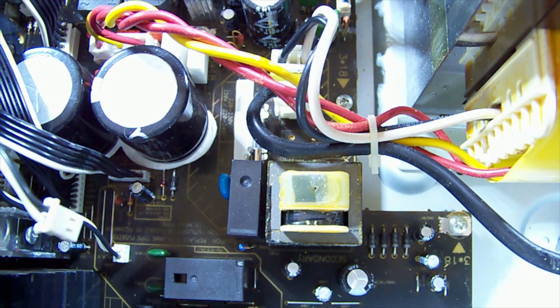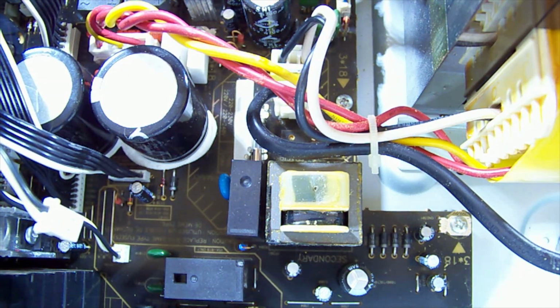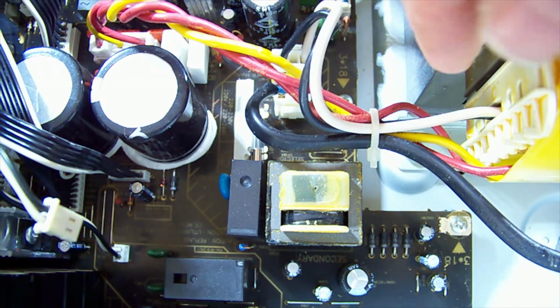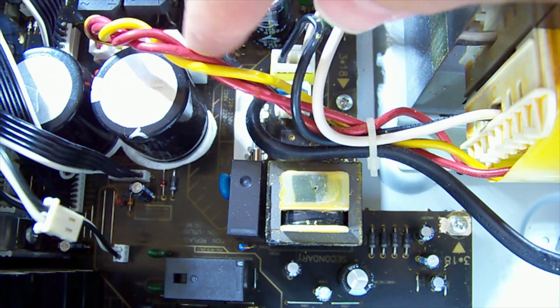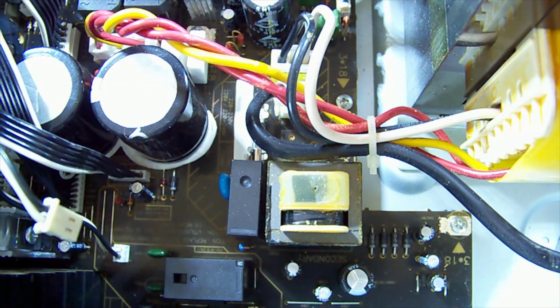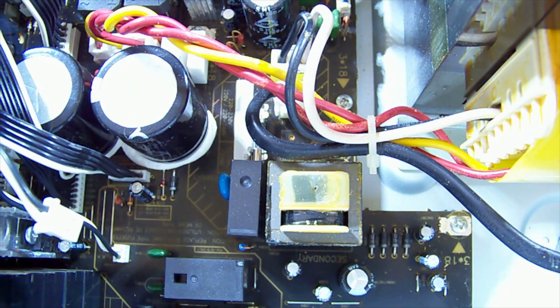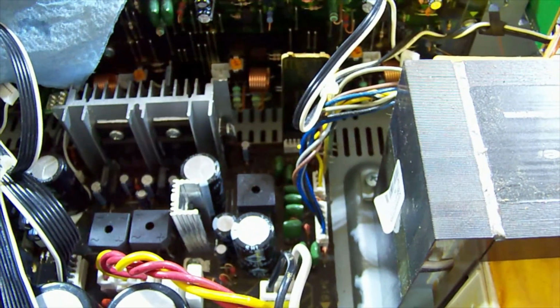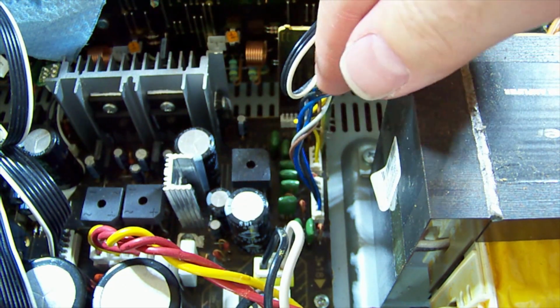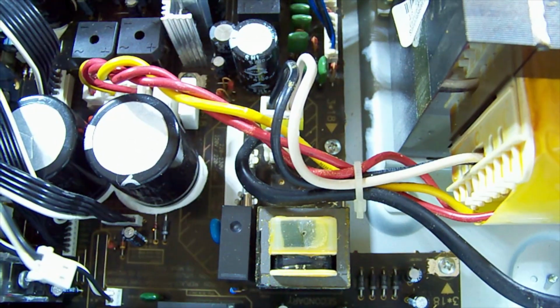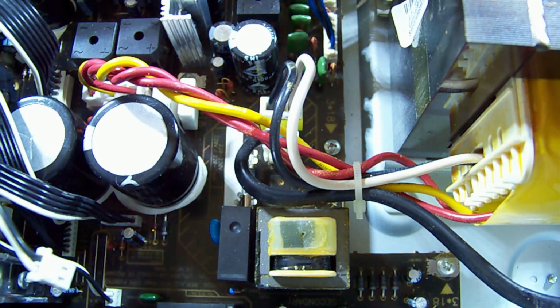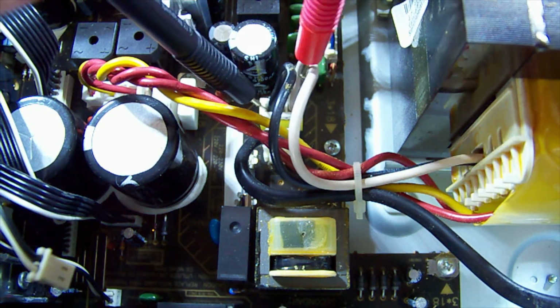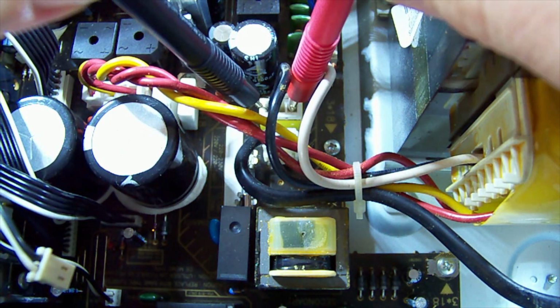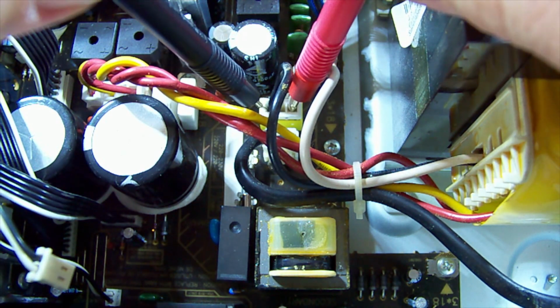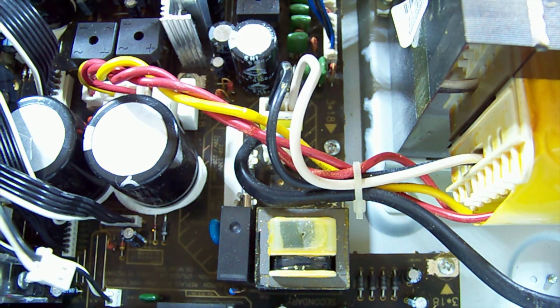So let's have a look. We can see that the black and white wire there goes into the transformer, so that's going to be our primary to the transformer. It looks like we've got a secondary tap coming off here. There's also another secondary tap on the other side of the transformer further up there. It's just this bunch of wires coming down here. So let us see, do we have power going to the primary side? I'm checking there. Okay, it appears we don't. So there's no voltage getting to the transformer.